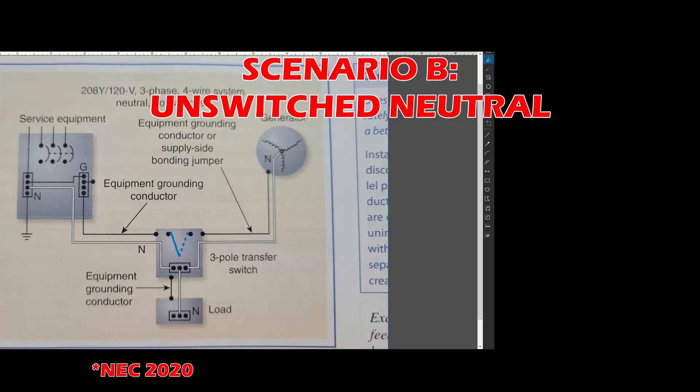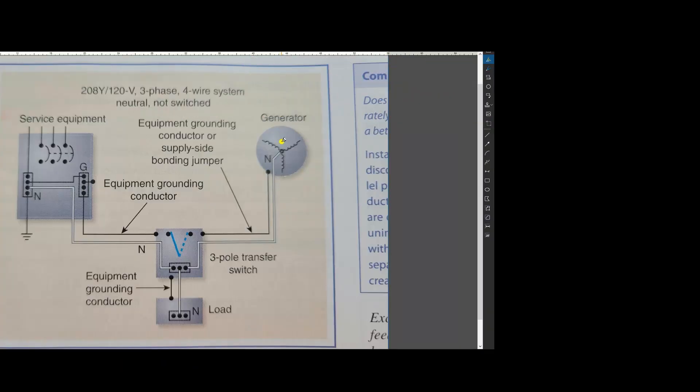In this scenario, the neutral wire is continuous. Follow the neutral wire with me. It originates at the generator and is continuous all the way back to the electrical panel. That means your transfer switch or interlock system never disconnects the neutral wire as shown here.